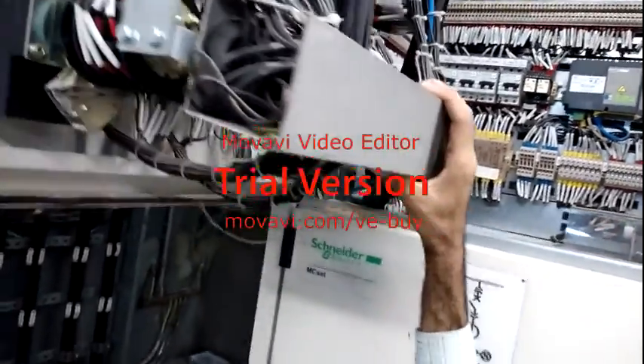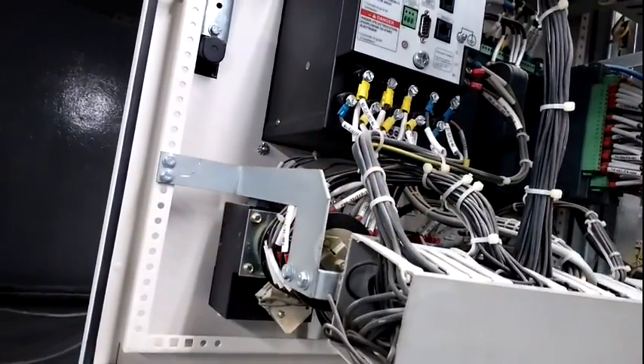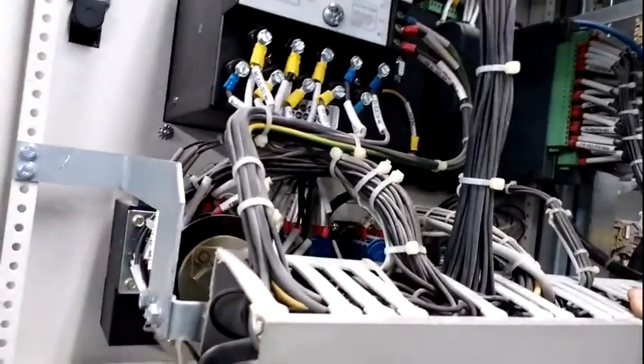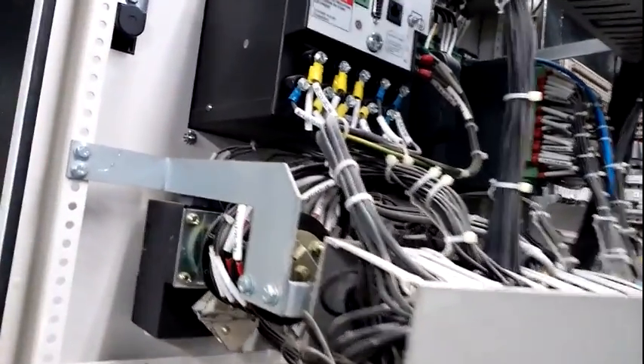Also there is another one for VTs. Both terminals are used for CTs and VTs, and we connect cables here: yellow cables for CTs and blue cables for VTs. You can see here on the multifunction meter, these are used for current measuring and for voltage measuring.